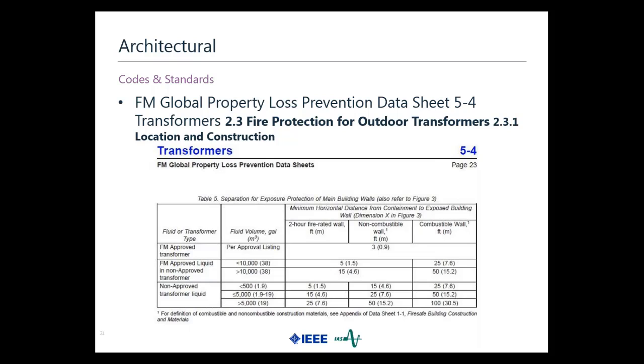We can go to the NEC, and if we've got a transformer inside a building, we know what to do with it—the NEC prescribes that. But a lot of times you get into the question: how close can I be if I'm outside? What kind of construction do I have to have? I'm not going to go over this in detail, but notice it's broken down by whether it's a non-flammable, approved liquid from FM, or a non-approved transformer liquid like mineral oil. Obviously the distance varies depending on what kind of fluid you have and how much is actually in it.